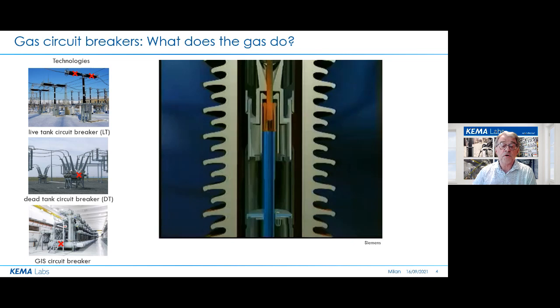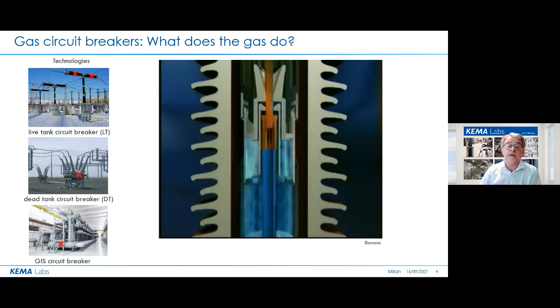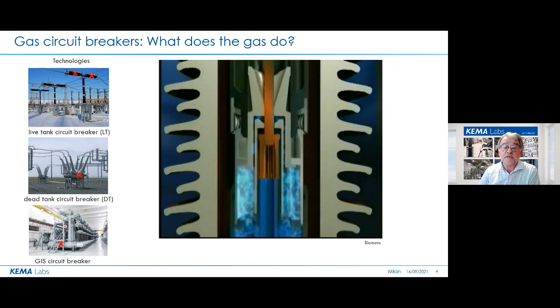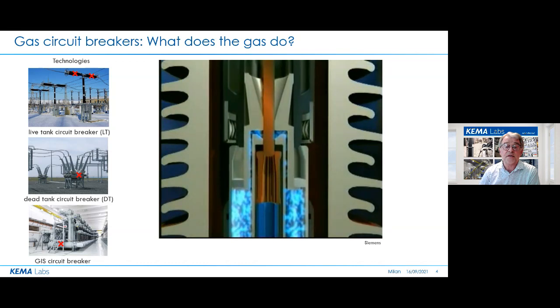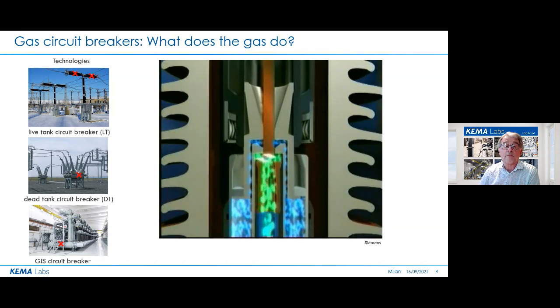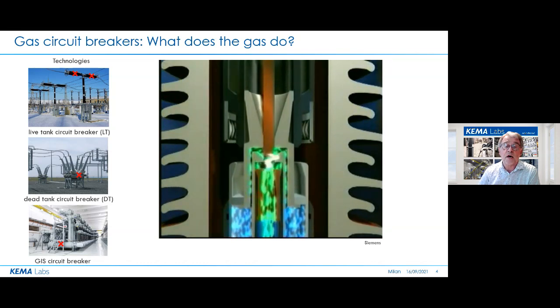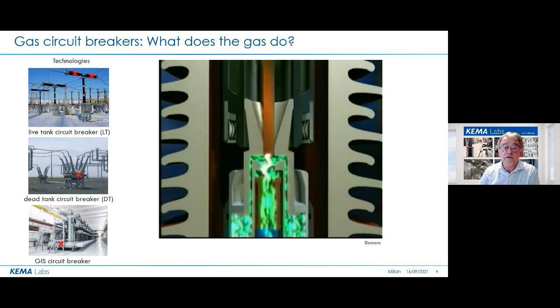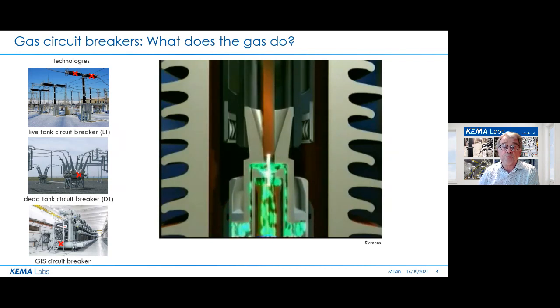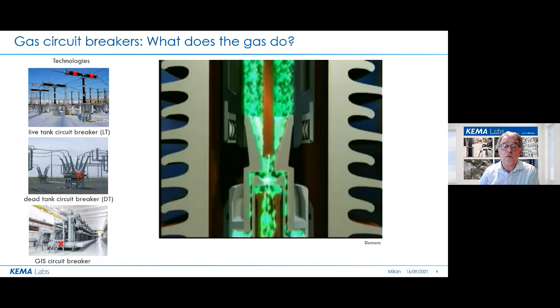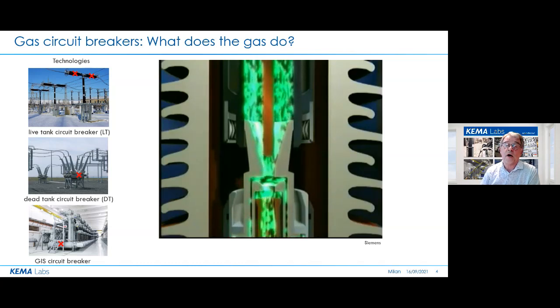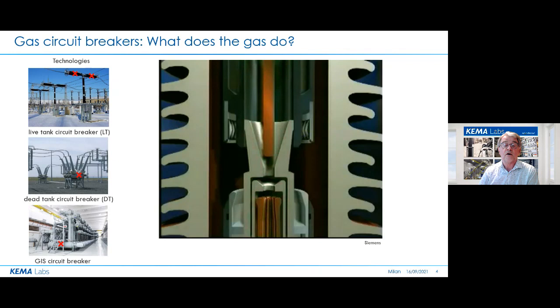Well, I will try to show now a working condition of this circuit breaker. So you see in the animation now how the gas during the interruption process is compressed, and as soon as the arc comes and when the nozzle is free, a high pressure of gas is flowing around the arc to cool the arc and to get rid of the remains of the hot plasma which is still inside. Well, this is one type of circuit breaker.